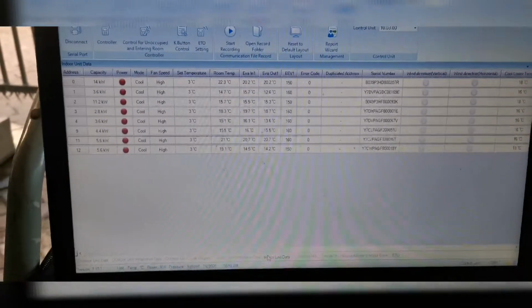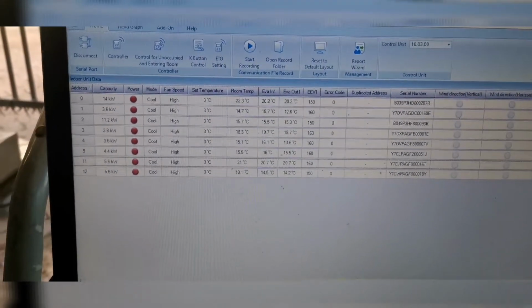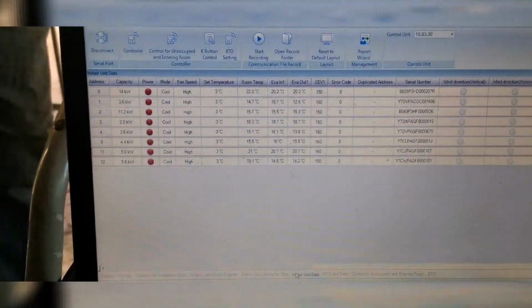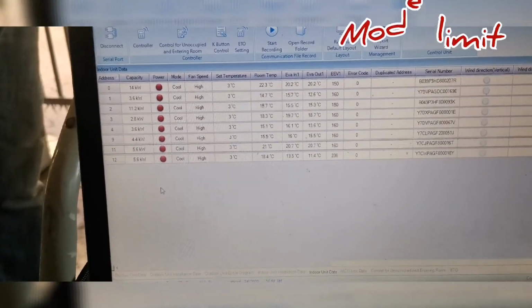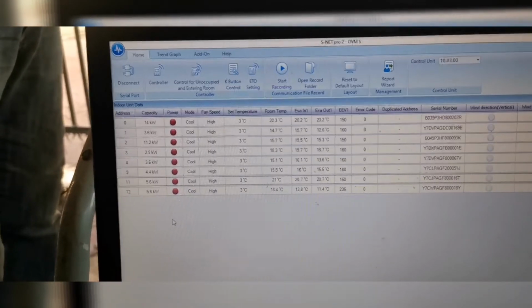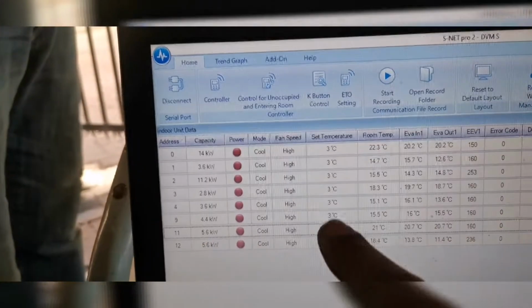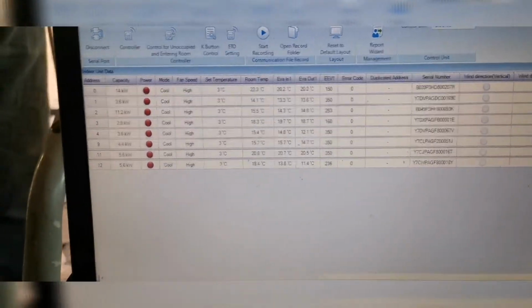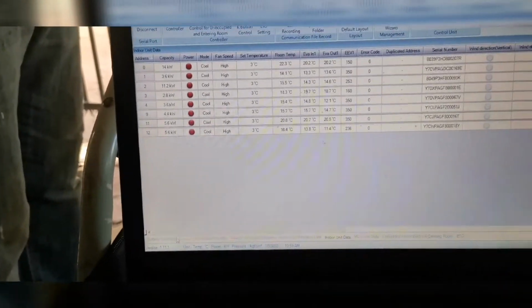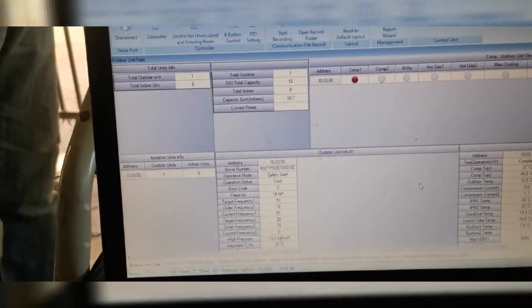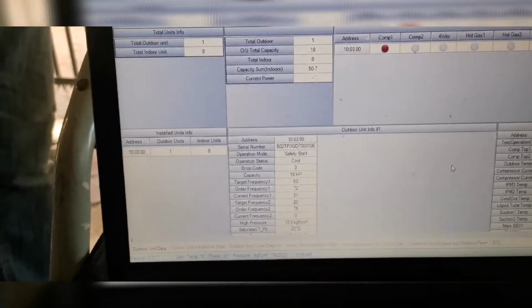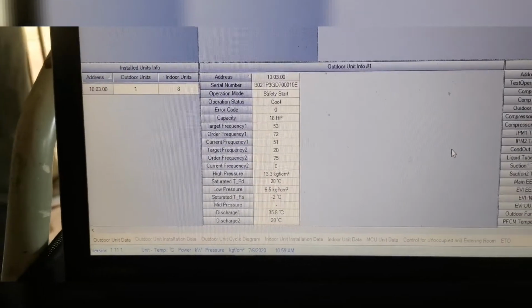Okay guys, so we were able to deactivate the limit that was set on the system. It was basically limiting it only to a heating mode. We removed that limit and we are now functioning in test operation, which is in the cooling mode. Let's have a look. That's why you'll see the set points are all set to 3 degrees. And the reason for that is so that the system doesn't satisfy or cycle out on temperature, so that if we do need to add additional gas, we can do so. So the system is in safety start, operation mode is in cooling, so all of that looks good. And we can now have a look at our temperatures right here and pressures as well.